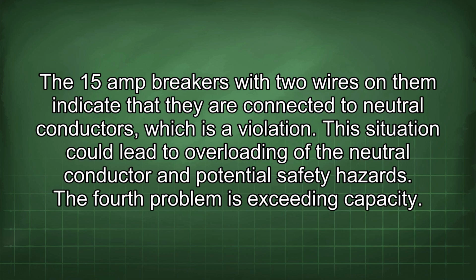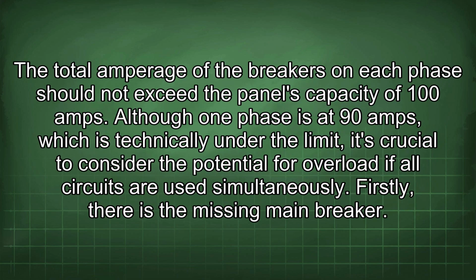The fourth problem is exceeding capacity. The total amperage of the breakers on each phase should not exceed the panel's capacity of 100 amps. Although one phase is at 90 amps, which is technically under the limit, it's crucial to consider the potential for overload if all circuits are used simultaneously.